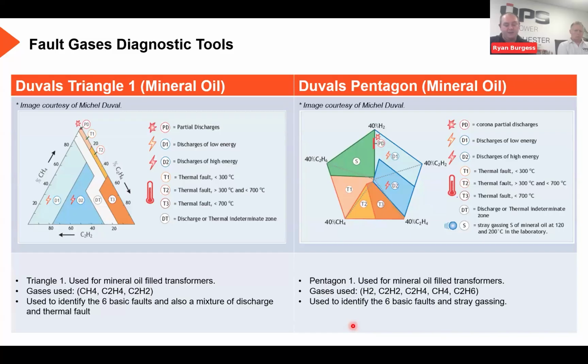And then finally, you can also use the oxide gases, which are the carbon monoxide and the carbon dioxide. Based on their ratio, that can determine how the paper insulation itself is degrading over time. It won't tell you the strength of the paper, we'll cover that in a moment, but it will tell you that there's degradation. And depending on the ratios, you can determine if it's due to overheating or just general aging. So just before we move on, the next thing we'll be looking at is furans, which will explain that oxide side better.